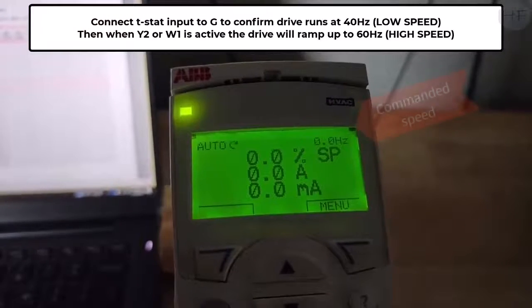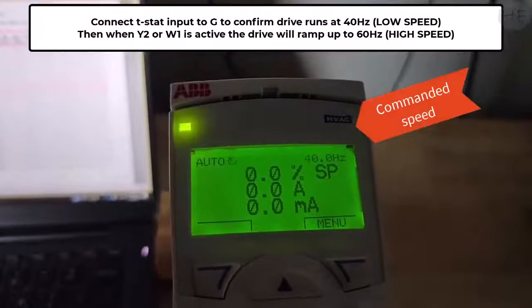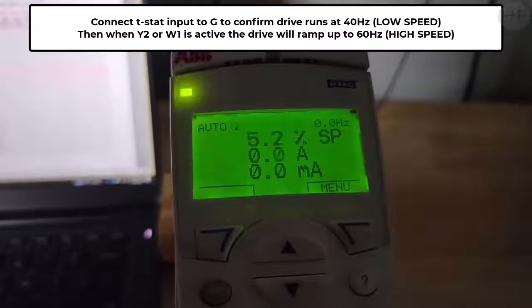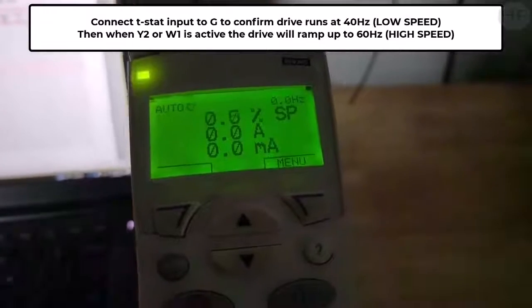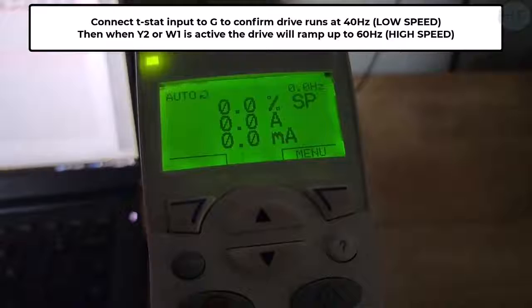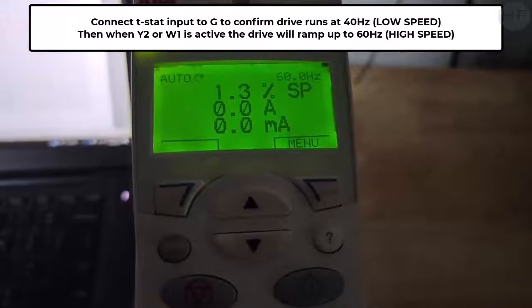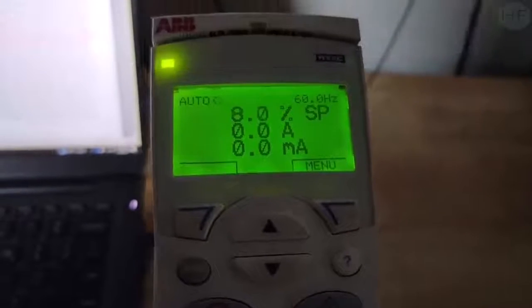Now you can test the drive by sending only a thermostat G signal to verify the drive commands 40Hz. Then send a thermostat Y2 or W1 signal to verify that the drive ramps up to 60Hz.